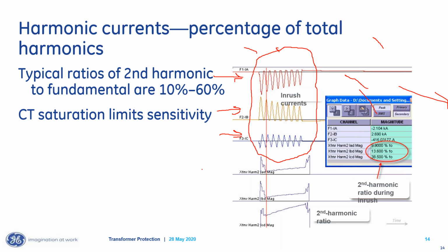The way that we typically do that is with harmonic restraint. Basically, the relay calculates, when we have these inrush events, because of the saturation of the transformer itself that's being caused by these inrush events, we see a lot of second harmonic content.